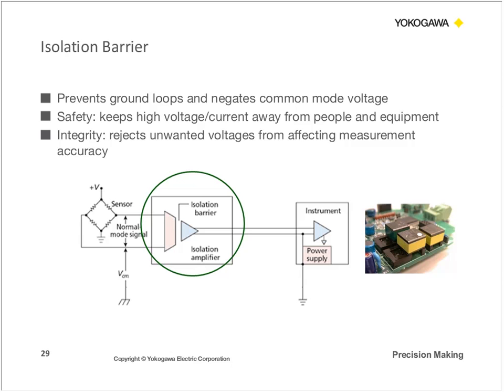And there are other added benefits as well. It's safe, so that if a transient occurs in your system and it does happen to flow through the device, it will not transfer over to the instrument. And if your user is operating the instrument at the same time, it's not going to harm him. The other thing it's going to do is help you to reject unwanted voltages or any offset voltage that can affect the measurement accuracy. So installing an isolator, or external isolation, is really one of the easiest ways to eliminate ground loop problems.